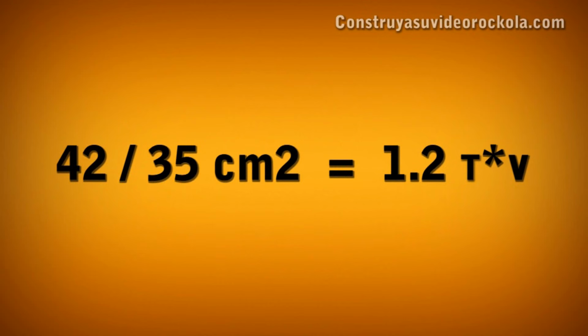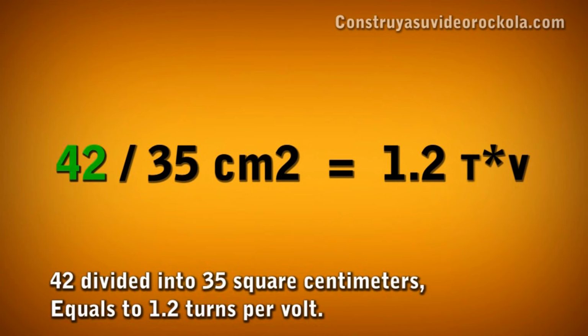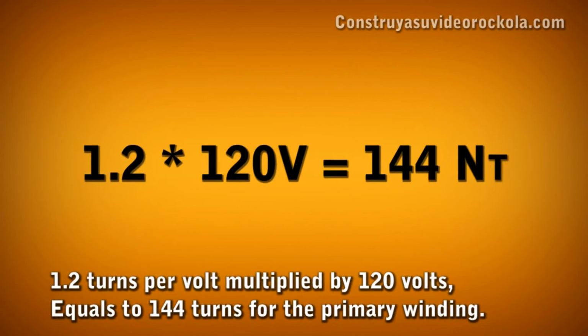Now let's apply the formula with the constant 42. 42 divided by 35 equals 1.2 turns per volt. Now we multiply 1.2 turns per volt by 120 volts of the public network of our country, and we get 144 turns for the primary winding.